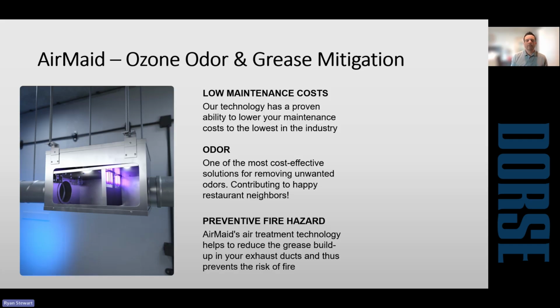And what you're going to see here, if you do have those real extensive duct runs, is much lower risk of fire, reduced duct cleaning requirements, reduced grease buildup on the louvers so the outside of the building looks nicer, and then of course the reduced odor.